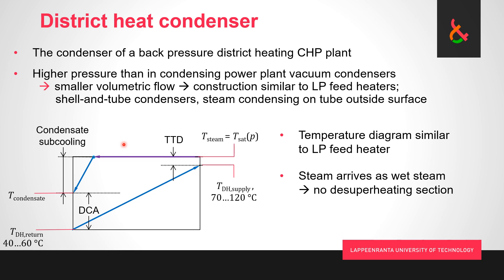In a condensing power plant it's a bad thing, but here we're dumping the energy into the district heating water, so we're producing district heat. We're doing it at the expense of power generation, but there can be situations where we want to do that. DCA drain cooler approach is similar to feed heaters, maybe 5 to 10 degrees Celsius typically.